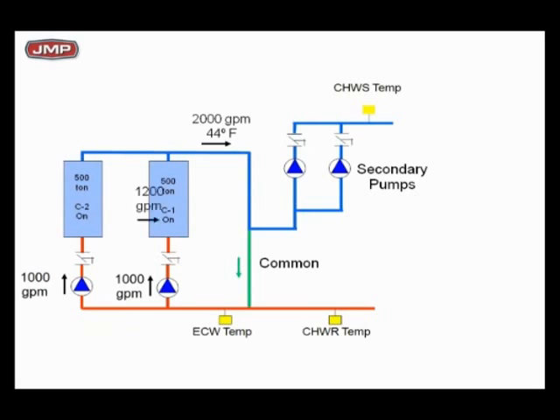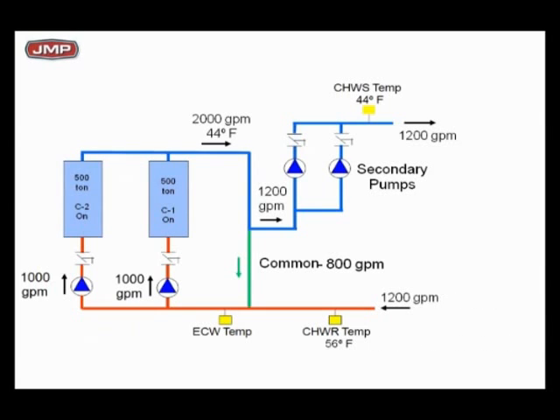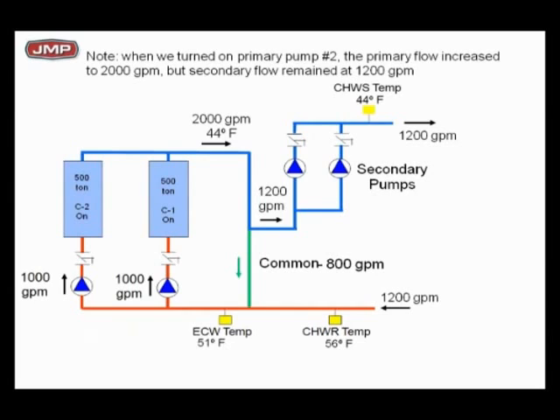Well, if you recognize, put the numbers up here real quick so I don't bore you with some of this. I've increased my flow to 2000 GPM at 44 degrees to the first T. I'm still taking out 1200, but now I've got 2000 going to the T, so now I've got going north to south 800 GPM of 44 degree water. I'm bringing my 1200 back at 56. So I'm mixing, and I wind up with each chiller seeing 51-degree return water. In other words, I've got 1,000 GPM of 44-degree water going out. I bring it back to the chillers at 51. So each chiller is seeing a delta T of, what would that be, 7 degrees.